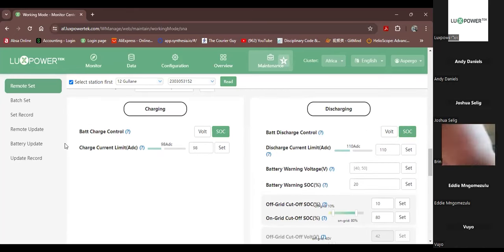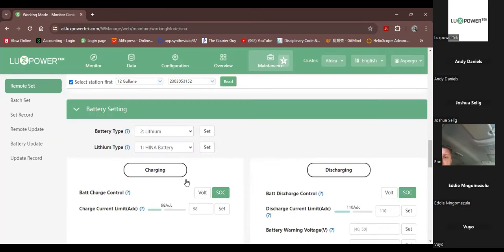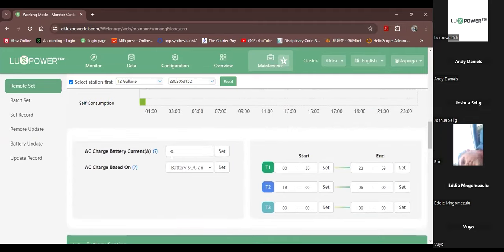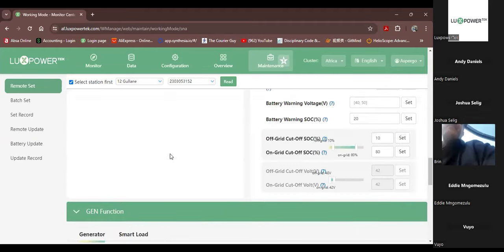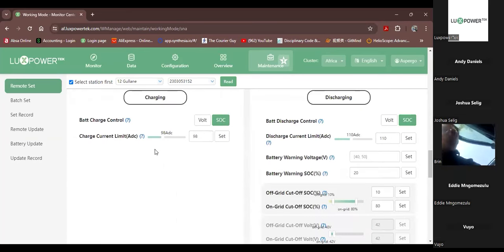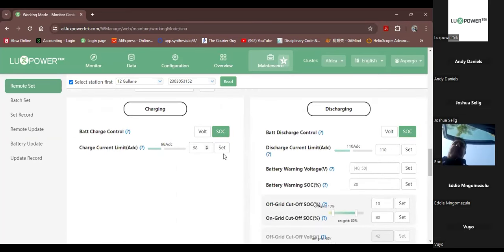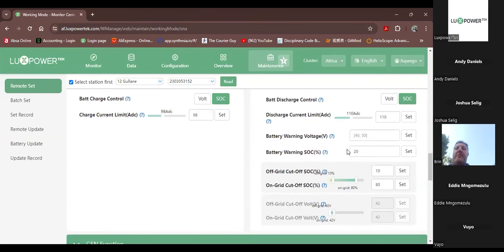And sorry, a quick reminder, you see that here we've got charge limit, right? This one was set at 110, I think it is. And here we've got 110. That's the default. And you must remember that's the total system charging. Okay, so this is not the AC charging. This is total system charging, which means that our AC charge here was set at 50 amps. That's AC. But here, this is DC amps, but the DC amps include PV because we can go up to that value when charging with PV.